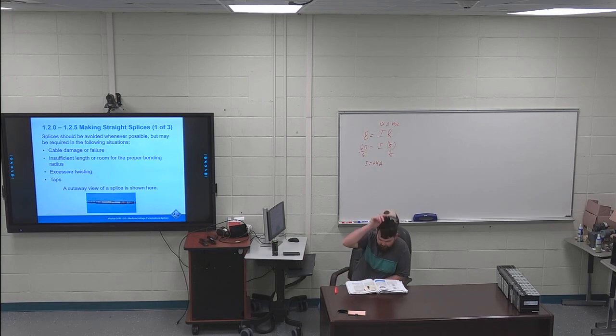Page 5, first paragraph, second sentence is highlighted. In general, the conductor jacket and insulation should be removed for 1/2 of the connector length plus 1/4 inch. So 1/2 of the connector length plus 1/4 inch.